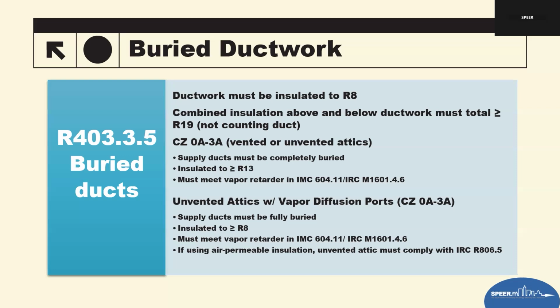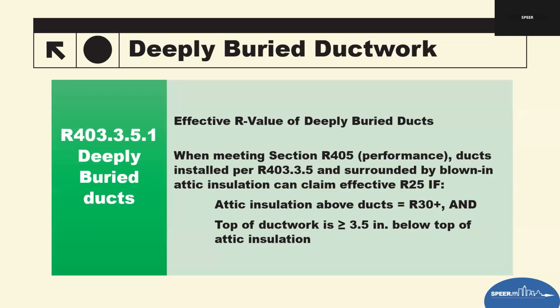So the big takeaway from that is the 2024 IECC brings much clearer requirements for buried ducts. The goal here is simple: reduced duct energy losses while preventing moisture problems in hot, humid climates. So proper insulation level, buried depth, and vapor diffusion control are now essential for compliance. I'll still put a caveat at the end that the IECC does not call out a requirement for a vapor diffusion port or vapor diffusion control. The IRC talks about it, but the IECC does not address that at this time. So just to clarify that part of it.